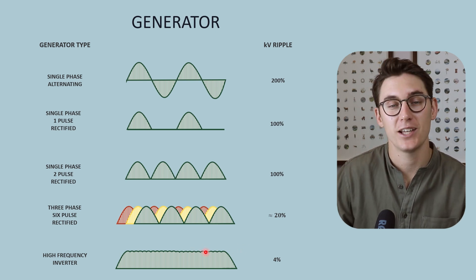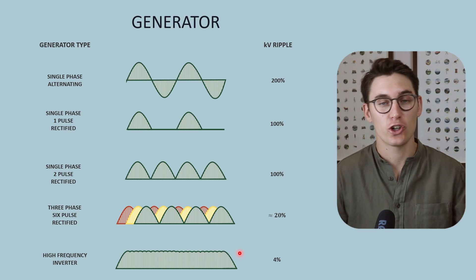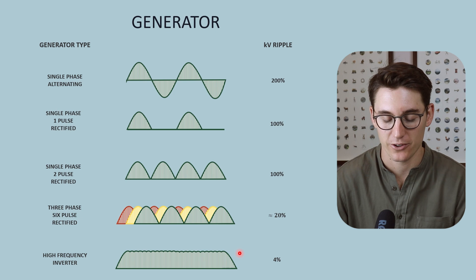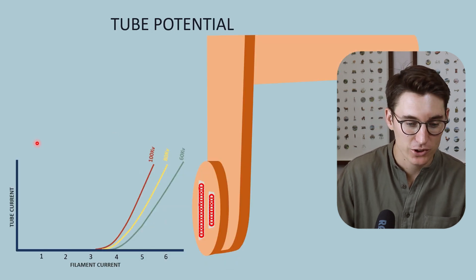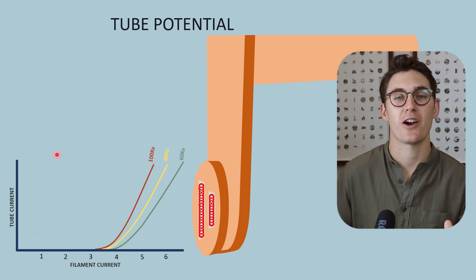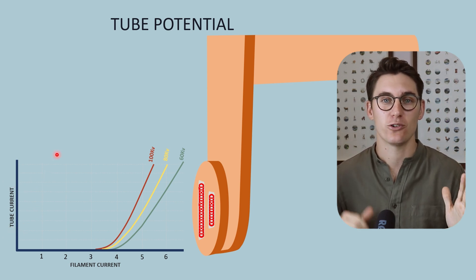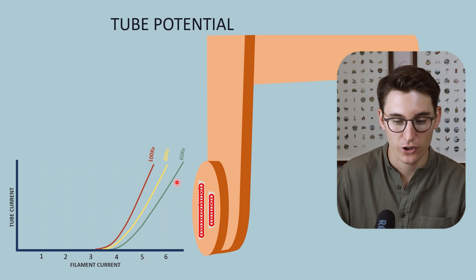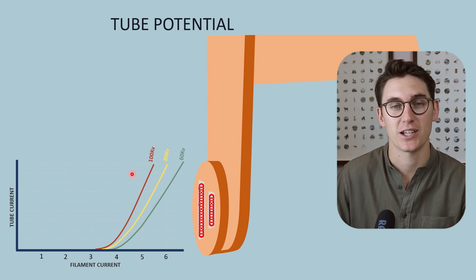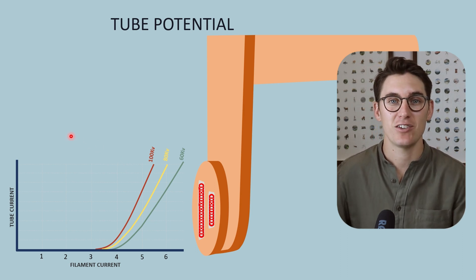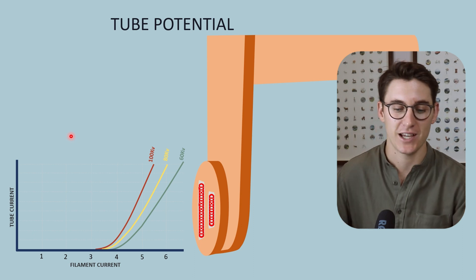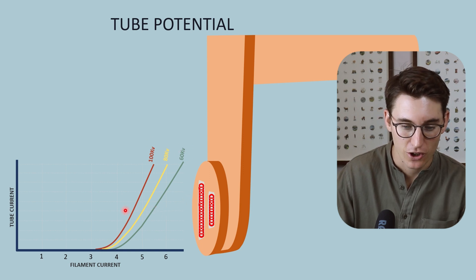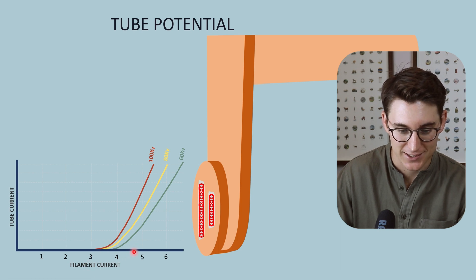Our kVp — our kilovoltage peak — determines the energy of the electrons going from cathode to anode, and also has an effect on the number of electrons flowing between them. Looking at a graph of tube current — the number of electrons flowing from the cathode to the anode over time — we can change two things to manipulate tube current. The first is increasing kVp by selecting a higher kVp in our primary circuit and stepping it up through the transformer. As we increase kVp, say from 60 to 80 to 100 kV, we get a shift of the graph to the left.